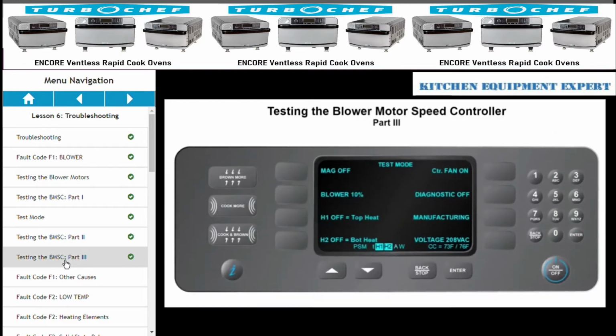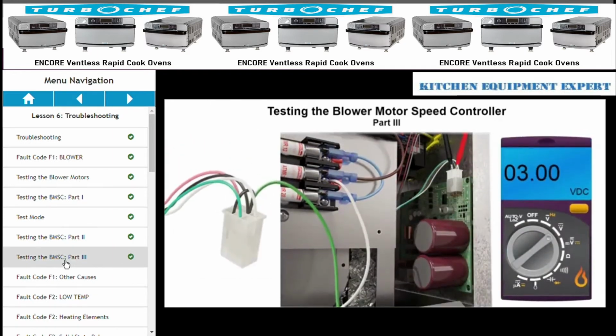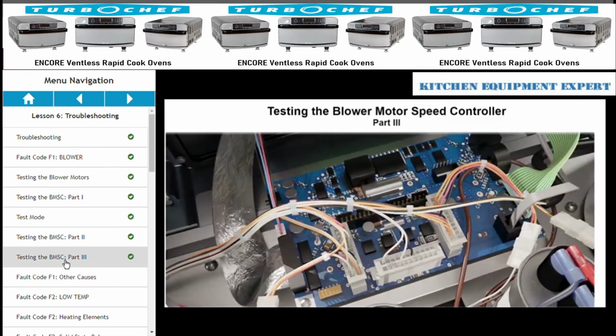Go to the keypad display that's still in test mode. Press the soft key next to blower 10% to increase the blower speed in 10% increments. Each increment should increase the voltage output from the main control board by 1 volt DC. If you don't see the correct voltage, check the wiring harness, and if that's okay, replace the main control board.